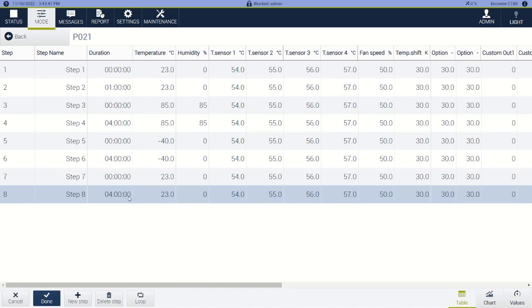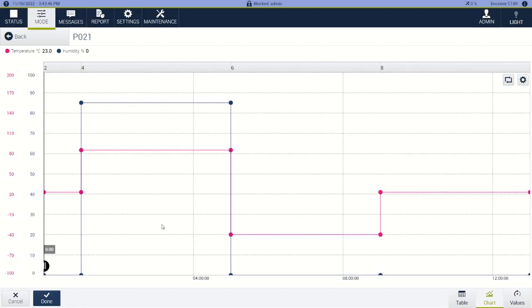So here's our profile, and we can double check what this looks like by going to the chart button over here. You can see temperature in pink and humidity in blue. Temperature goes from ambient to 85, to minus 40, back to ambient. And then humidity: 0 for temperature only, 85%, then 0 for uncontrolled. So that's one loop.